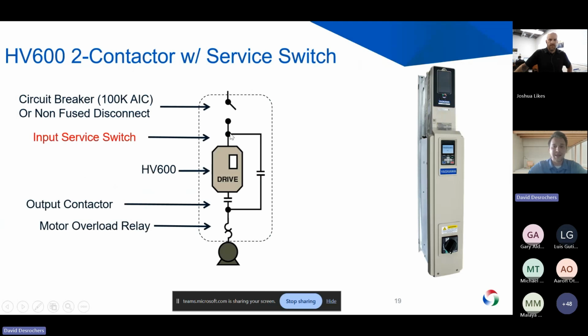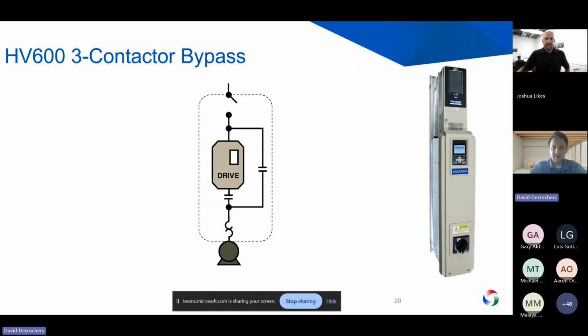In the same vein, we can also do one with a service switch. My graphics in the last 10 minutes before I was trying to get this going got switched up, and so I'm missing my switch here. But as you can imagine, there'd be a switch right here, along with your circuit breaker, and then the same contactors we discussed before. This allows you to disconnect power fully from this drive up top if you like. It reduces wasted energy by not having to keep that DC bus powered up. Just another option, depending on what your spec calls for.